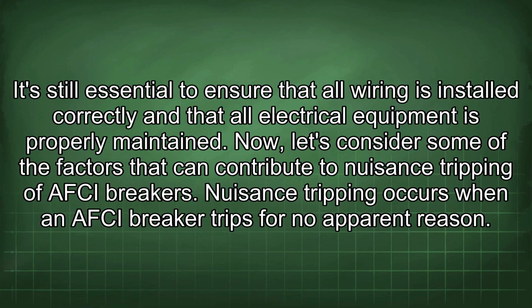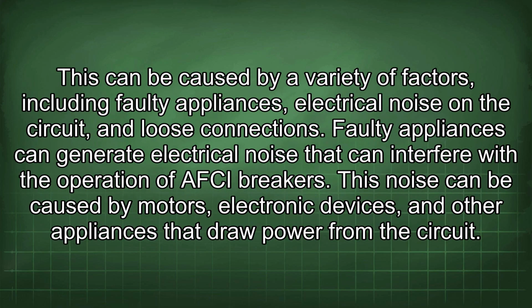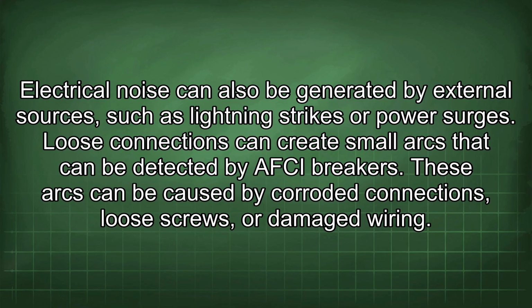Now, let's consider some of the factors that can contribute to nuisance tripping of AFCI breakers. Nuisance tripping occurs when an AFCI breaker trips for no apparent reason. This can be caused by a variety of factors, including faulty appliances, electrical noise on the circuit, and loose connections. Faulty appliances can generate electrical noise that can interfere with the operation of AFCI breakers. This noise can be caused by motors, electronic devices, and other appliances that draw power from the circuit. Electrical noise can also be generated by external sources, such as lightning strikes or power surges. Loose connections can create small arcs that can be detected by AFCI breakers. These arcs can be caused by corroded connections, loose screws, or damaged wiring.